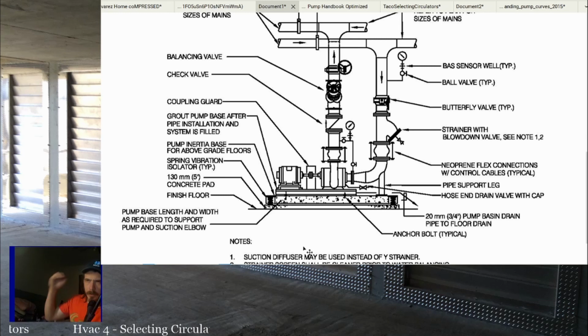All right. If you've got no flex connector, the pump is going to transmit that vibration into the piping system. And where those things are connected, you're going to increase the possibility of leaks. Honestly, compressors are the same thing. Really, it would be great in AC systems if we had flex connectors on compressors more often. And on large AC compressors, you will see flex connectors because compressors transmit vibration. Anything that's connected to piping is going to transmit vibration to the piping unless you have some sort of flex connector there to absorb that vibration. So even on small residential, it's not a bad idea to have flex connectors on your pump.